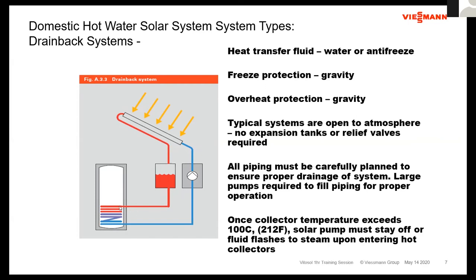Once this tank gets up to temperature, what happens is the pump here stops, and all of the fluid will now drain back into the conditioned space, so we don't have anything exposed up here that will freeze and cause some sort of failure. So I've basically had a look at what we're looking at here for a system. Your heat transfer fluid is typically going to be water in these systems. That's the advantage of the drain back, is it can just be water.